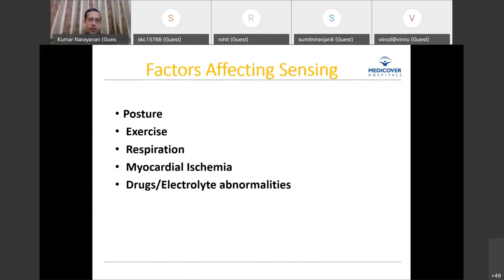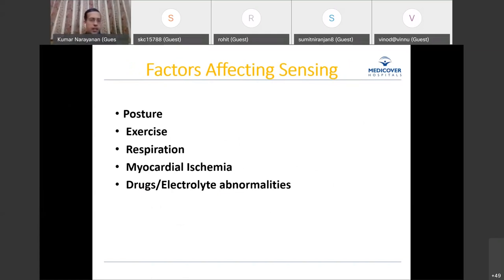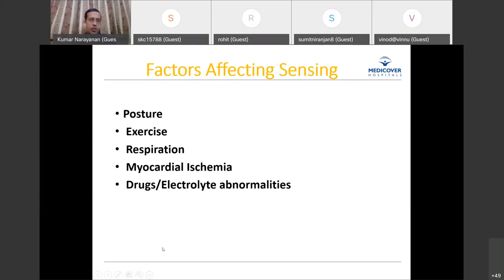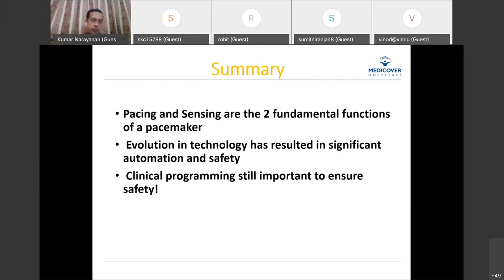Just as with pacing, various factors within the body can also affect sensing — posture, exercise, respiration, myocardial changes, drugs, and electrolyte abnormalities. Biological factors and changes in the patient's clinical status can affect the sensed signal, so these must be kept in mind when evaluating sensing problems.